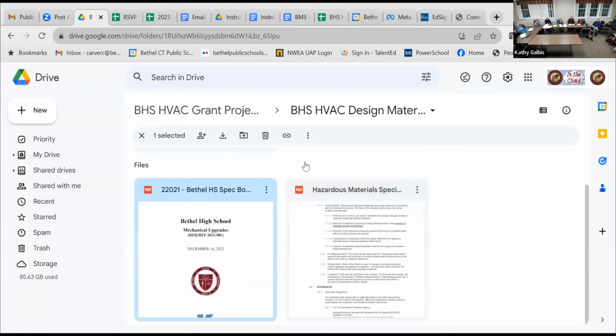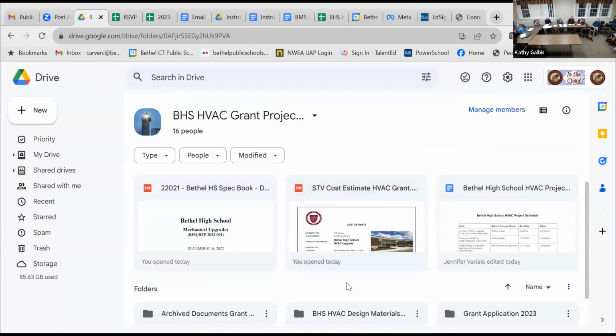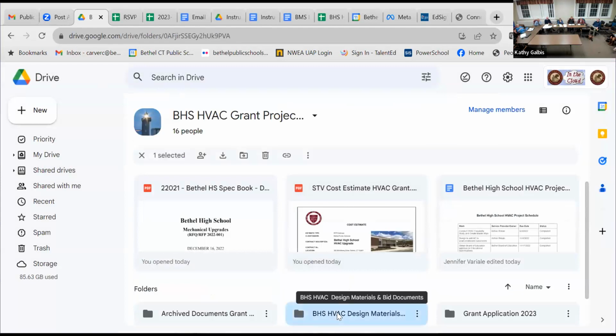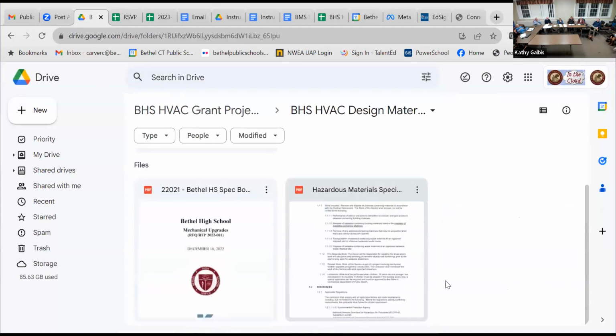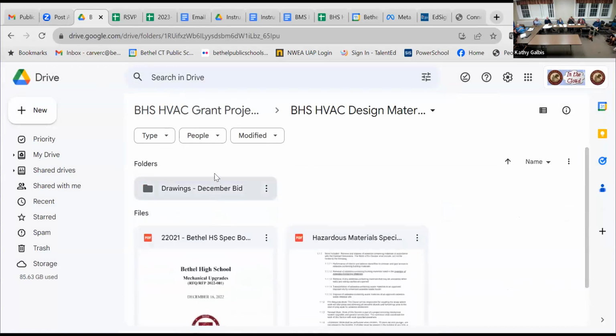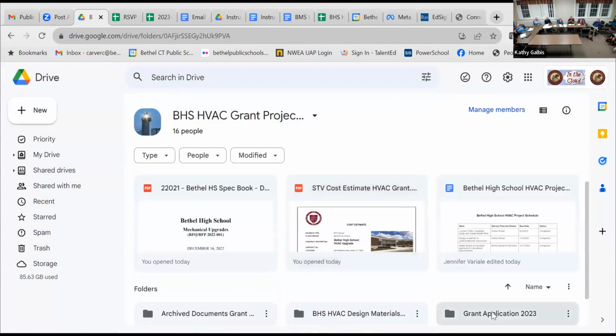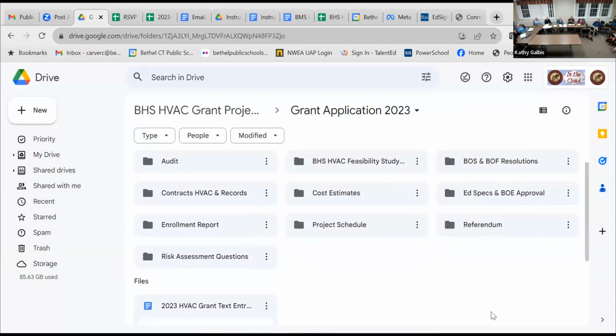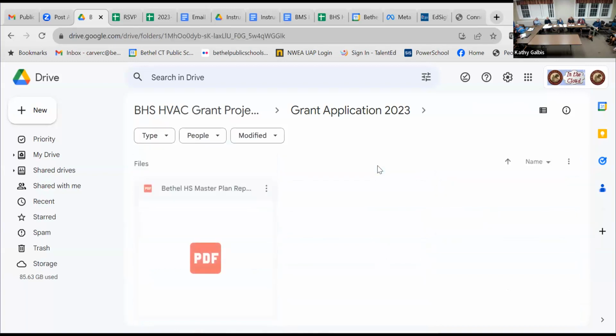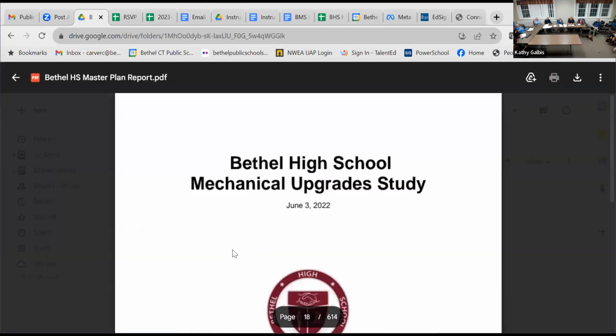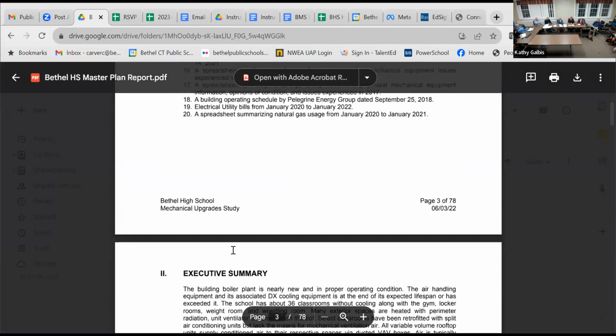You would never do a retrofit on a VAV. We have 22 schools and we haven't done a single retrofit to VAV because it's the biggest amount of equipment to put above the ceiling. I would much rather see, and just speaking for myself, the concept of running Freon lines to every classroom versus running chill water lines to every classroom.